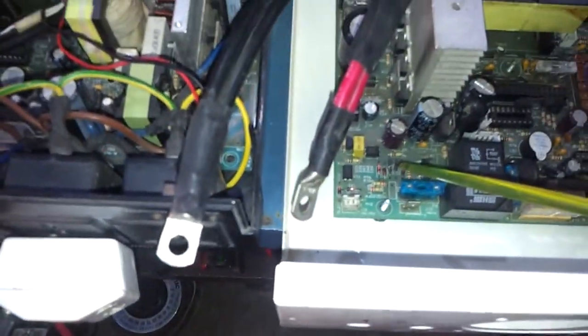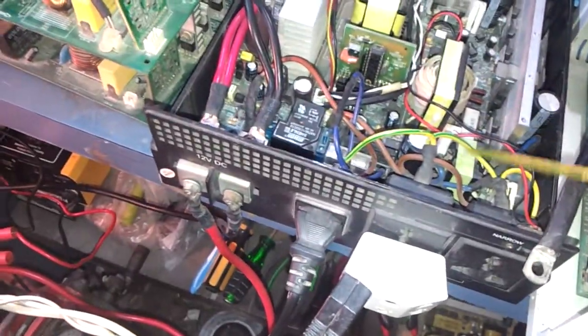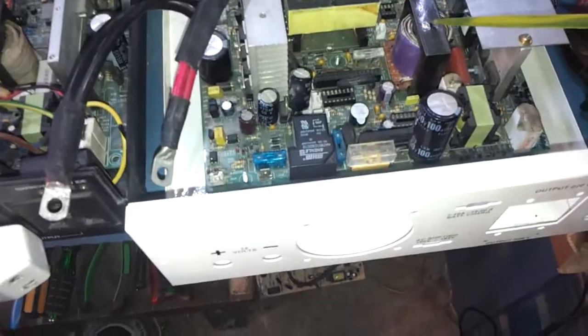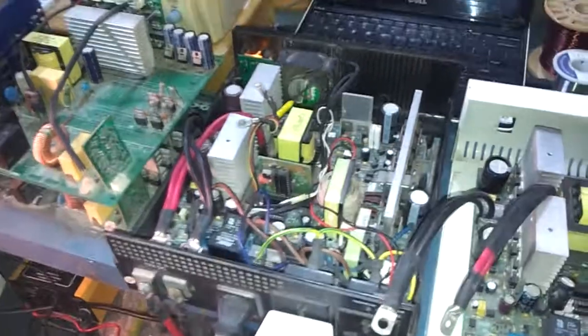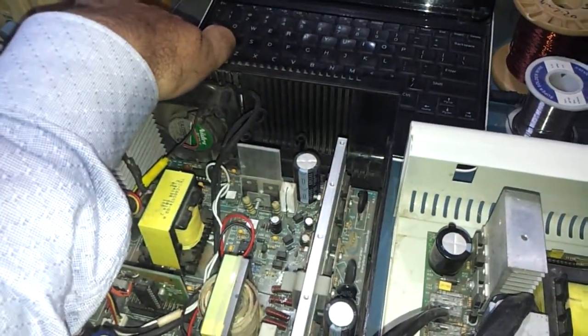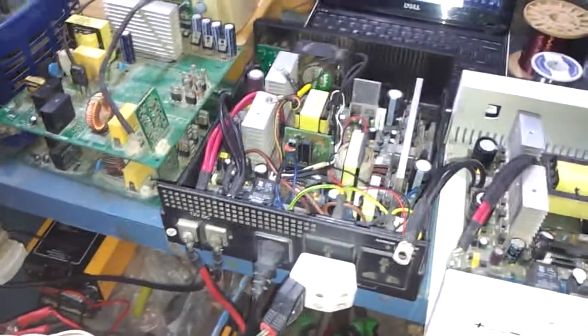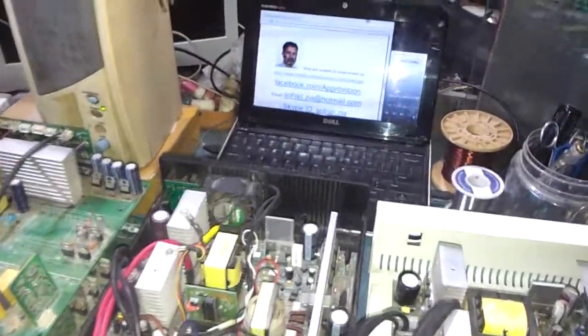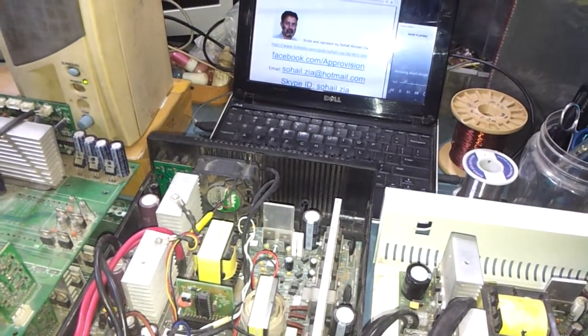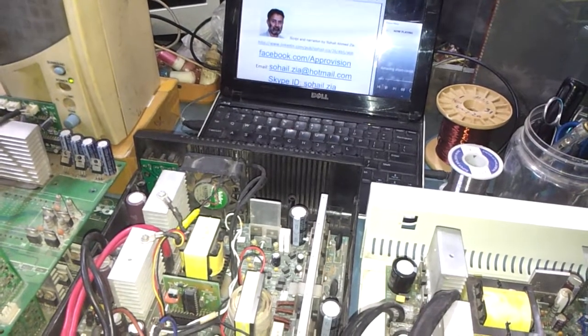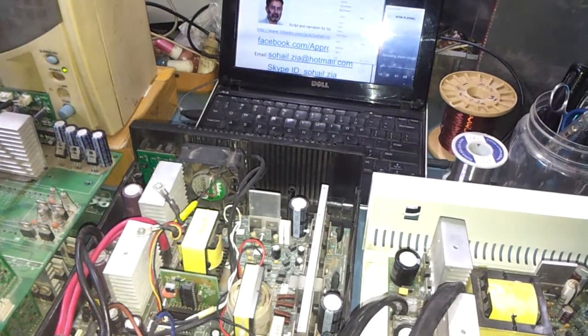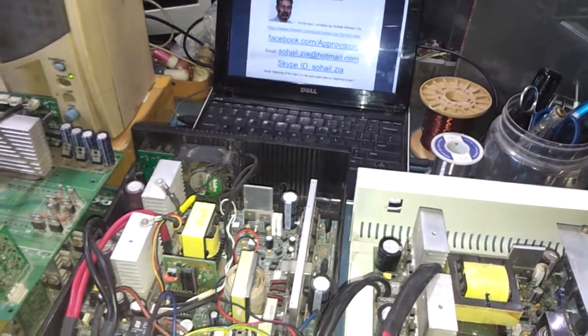The automatic charger in this UPS is constant current type to make fast charging possible without damaging the battery. The charger prevents overcharging and overheating of the battery with an intelligent float boost cycle. This ensures long battery life and prevents sudden death of battery. The charger can be set for 2 current values by a selector switch as desired. The 2 values from 5 amperes to 20 amperes.